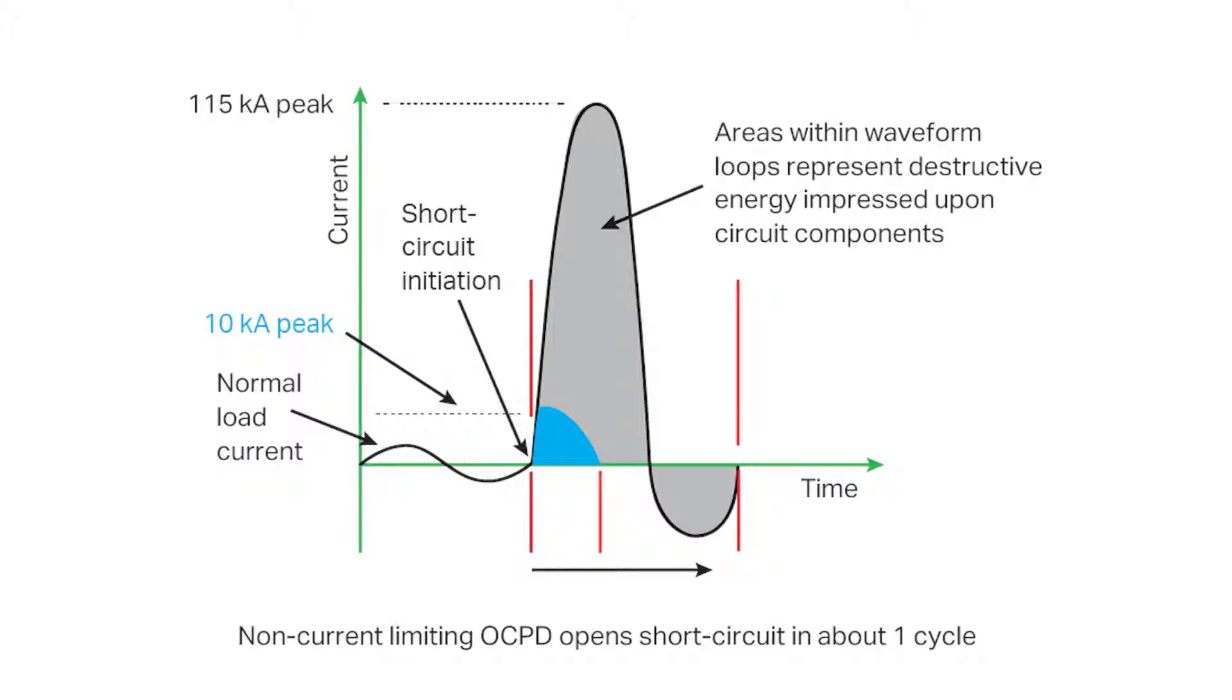A non-current limiting overcurrent protective device permits fault current to build up to its full value and lets through an immense amount of destructive current, heat, and magnetic energy before opening. Some overcurrent protective devices will permit short circuit currents to flow for more than one cycle.